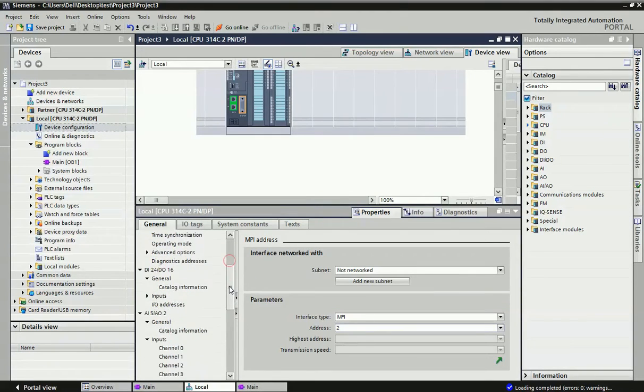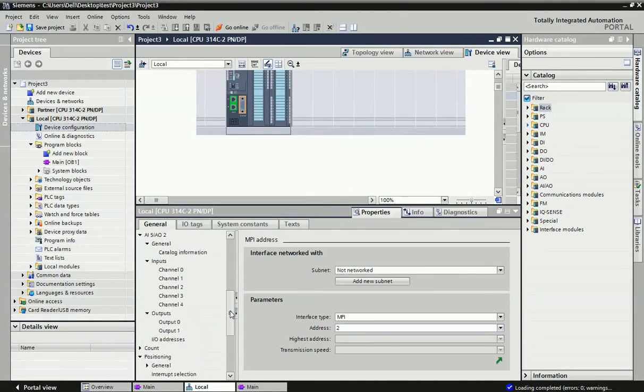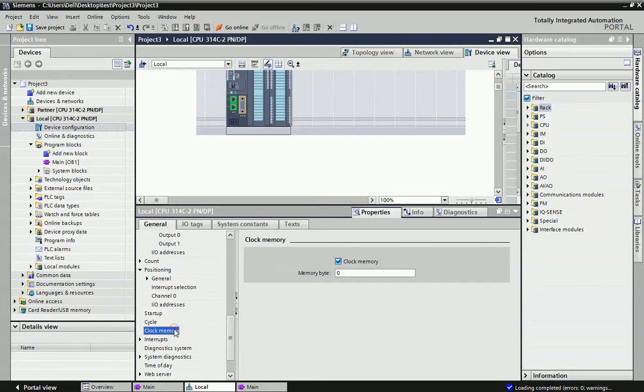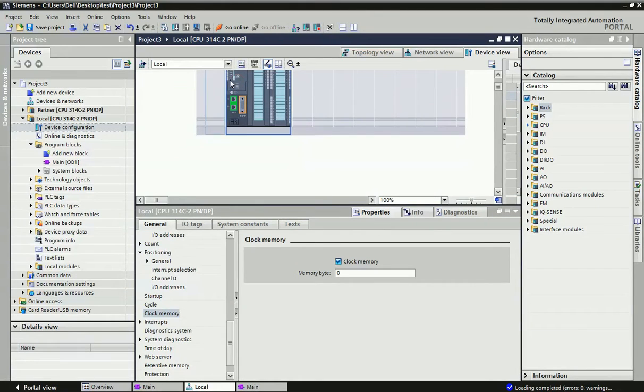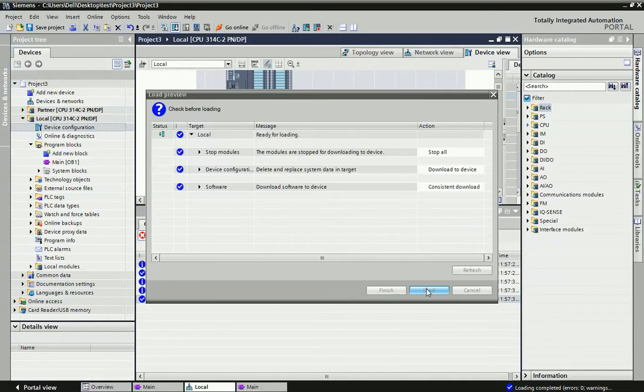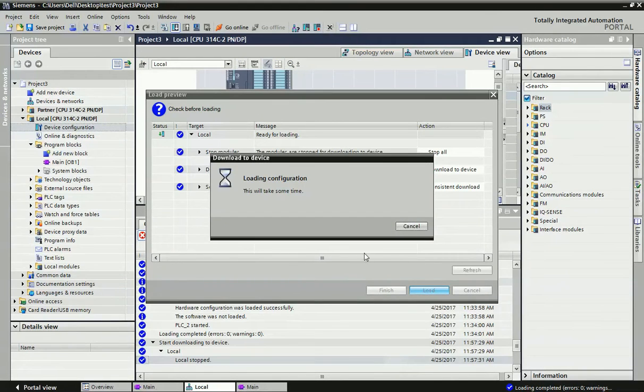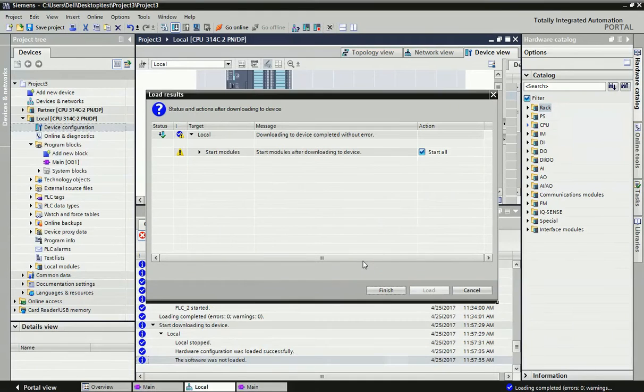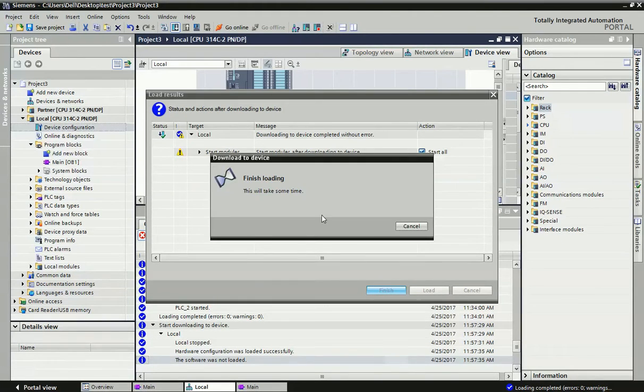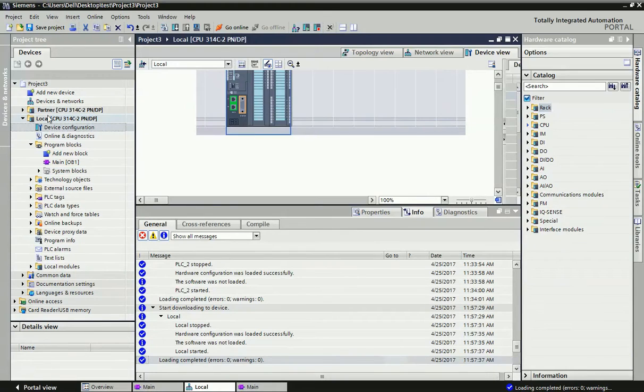Here we get the clock memory option. We enable clock memory and set memory byte zero, giving us M0.0 through M0.7 — a total of 8-bit clock memory. Then we download this configuration to the PLC hardware so the clock memory is enabled and the MPI address is set.